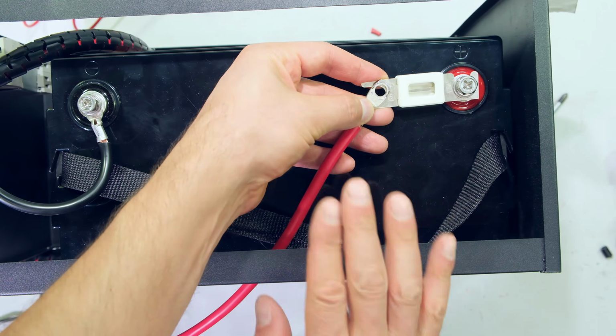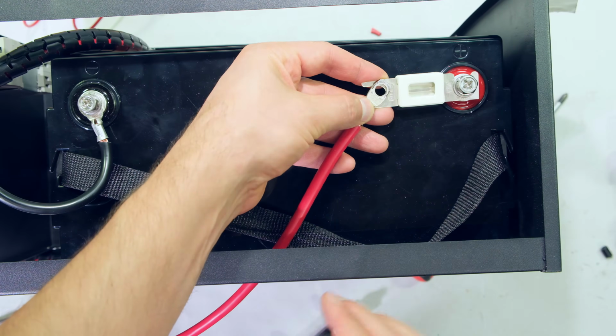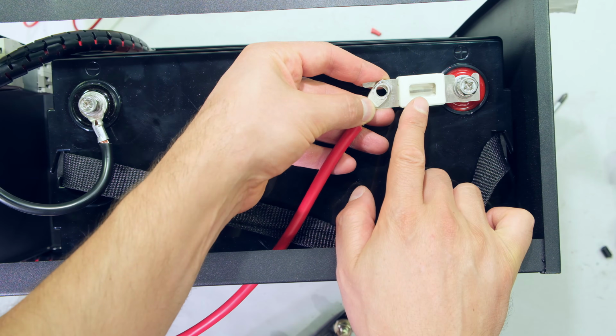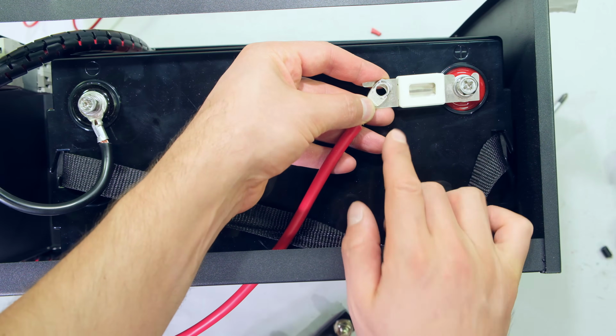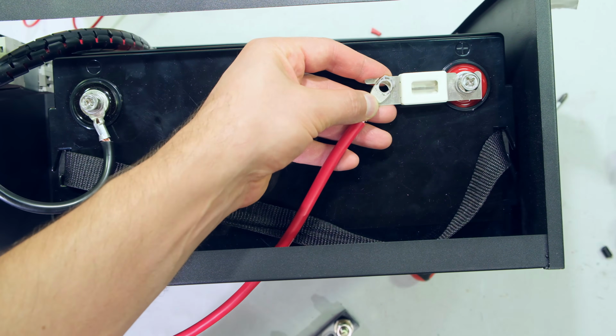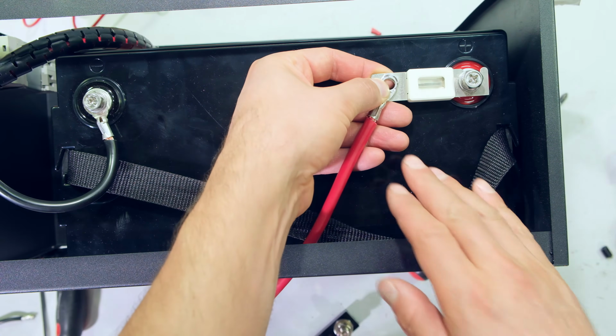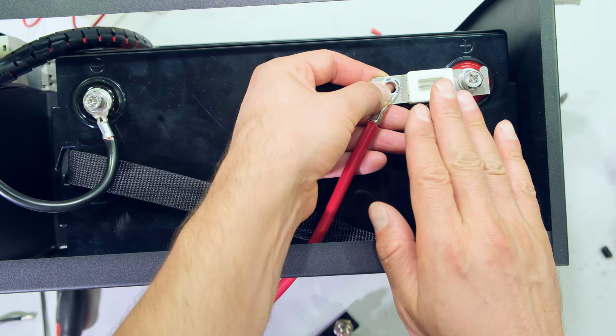Can I use the fuse just by itself with no circuit breaker? Absolutely. Just make sure that the fuse rating is low enough to protect the inverter. In this case, I would use a 50 amp fuse for this installation. So if I'm just using a fuse, I would have the fuse here rated at 50 amps.